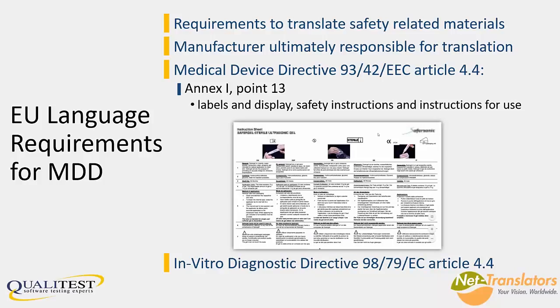Device manufacturers that intend to place their products in the European market must carefully comply with all essential requirements in Annex 1 to Directive 93/42 on medical devices, as well as with the member states' own legislation. The directive provides that member states may require the accompanying information to a medical device to be in their national language or in another community language. All member states require that safety information be provided in their official language to ensure understanding by the final user.